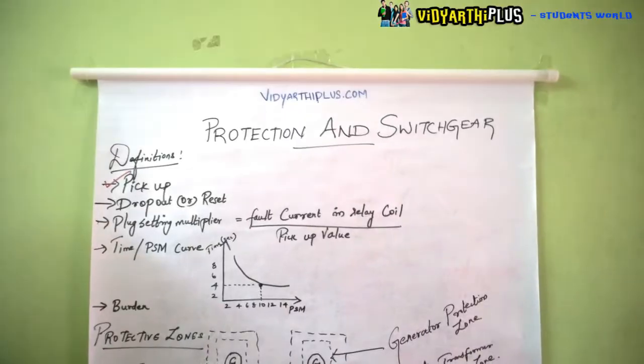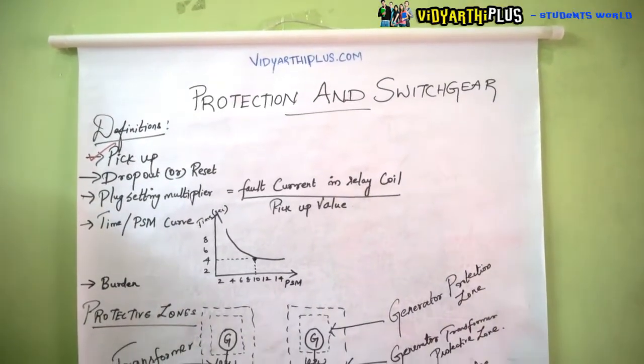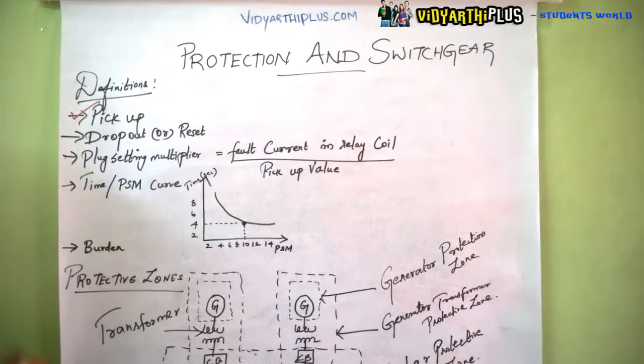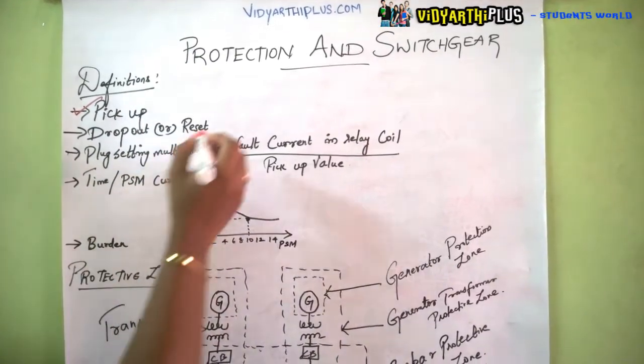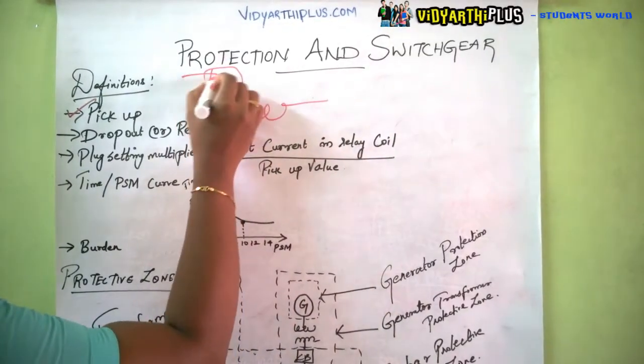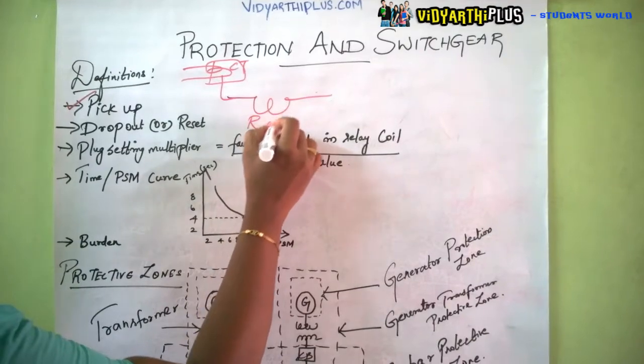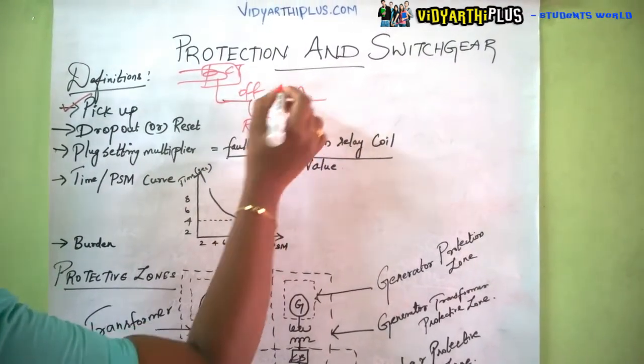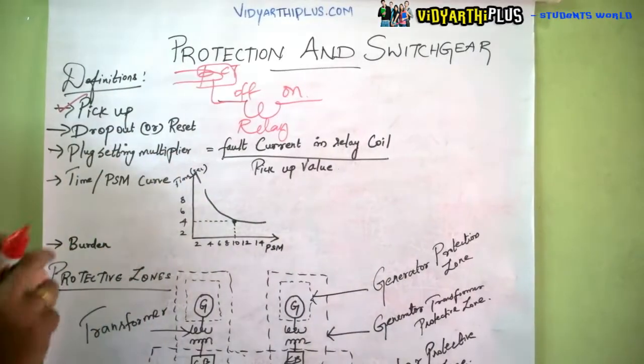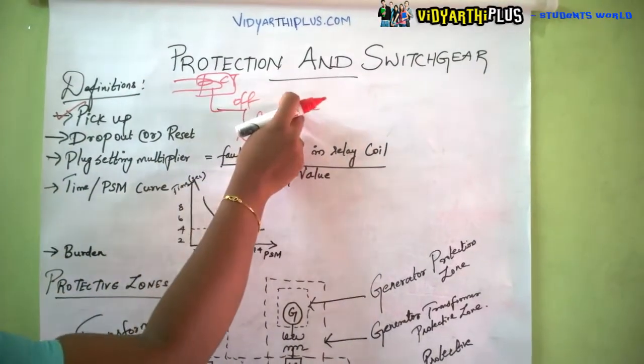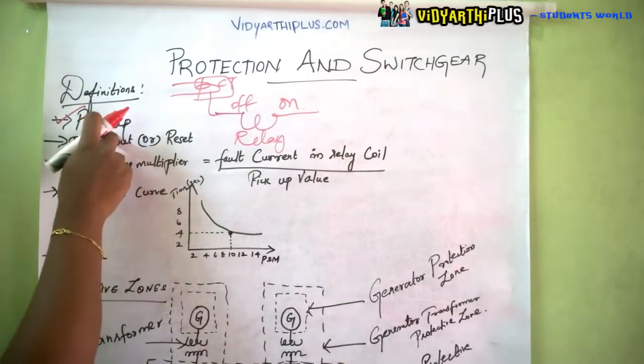The first definition is pick up, which is concerned with the relay. The relay senses the fault via a current transformer and goes from off to on position. The minimum actuating current at which the relay goes from off to on position is called the pick up value.